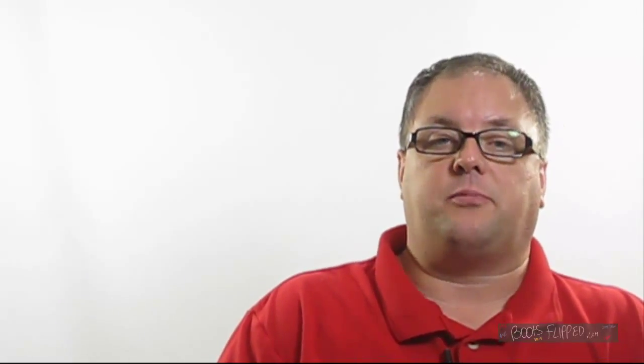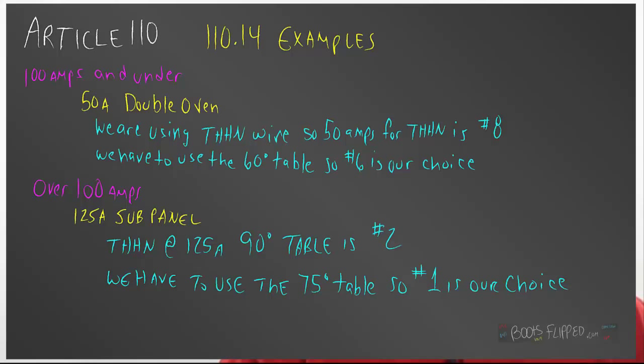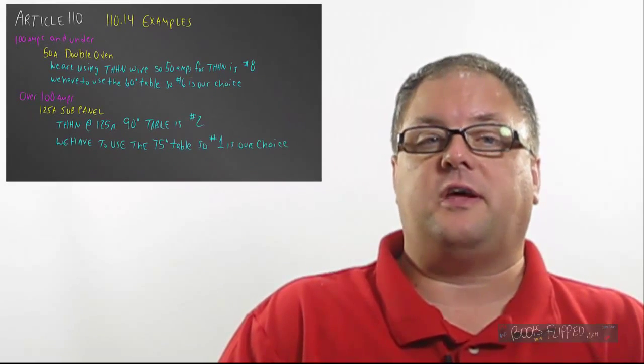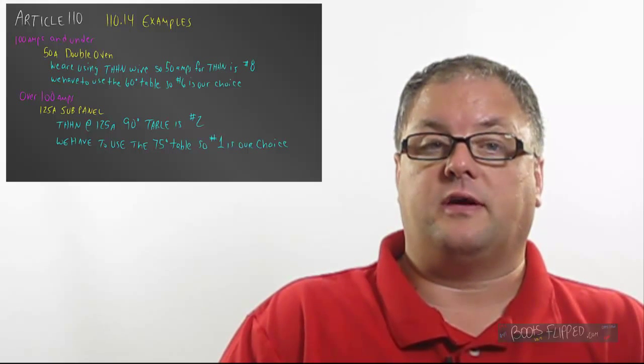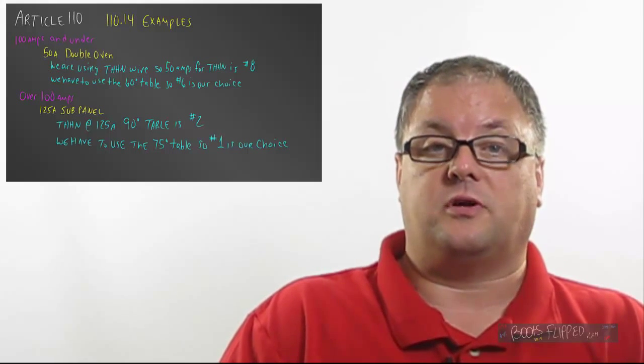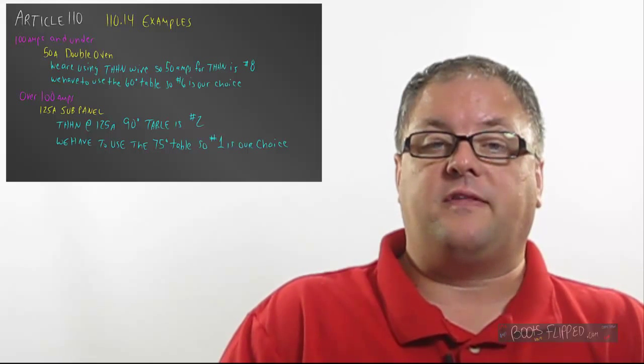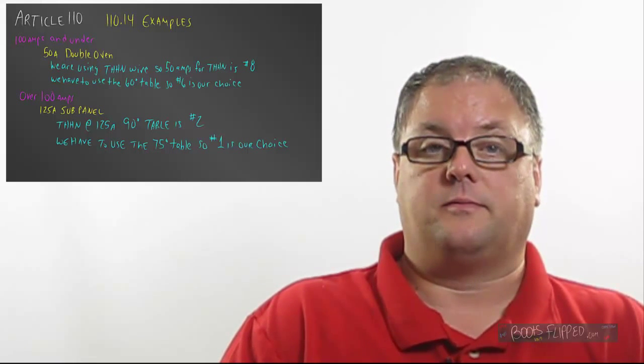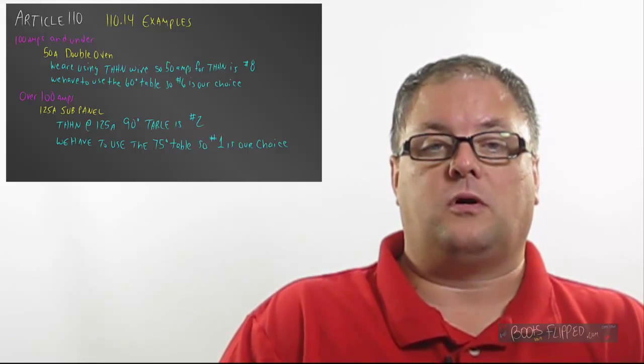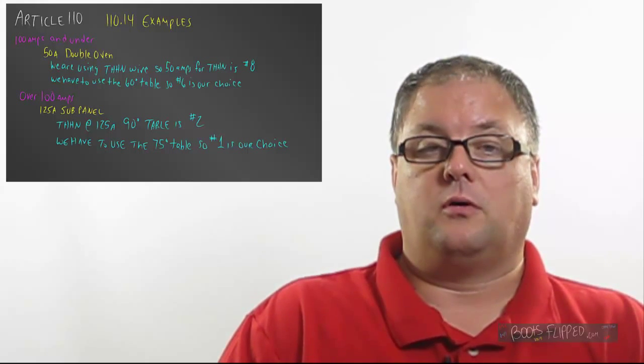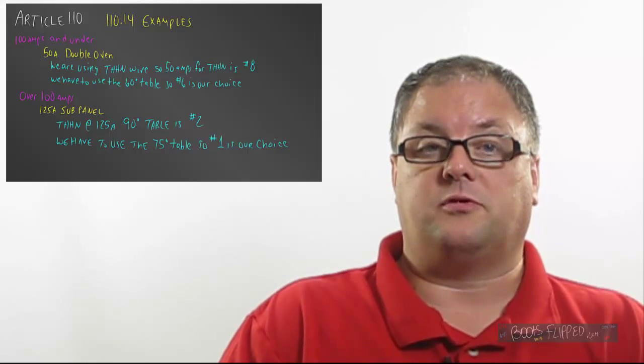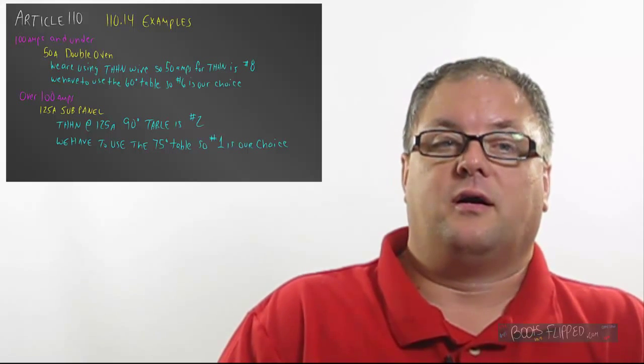So let's look at an example. If I had a double oven that I was putting in a house and it was 50 amps, or that was the size of the circuit that I had to run to it. So if I look at table 310.15B16, and I look in the THHN column because that's what I'm running, I'm going to find that I could use a number 8. Well, according to this code, though, I have to look at the 60-degree table, which is going to make me use a number 6.